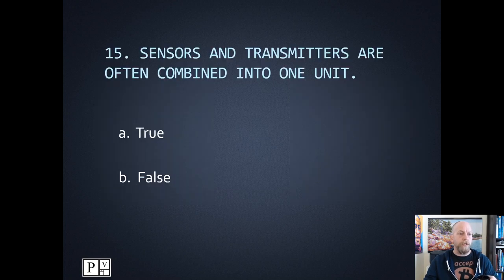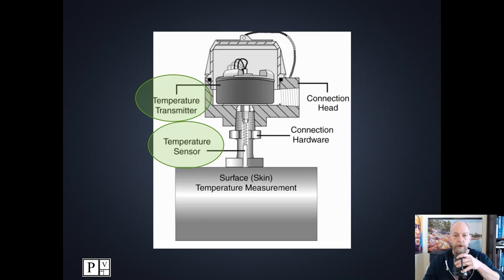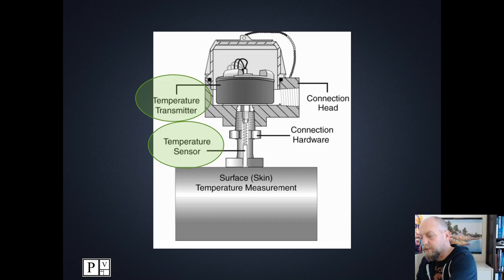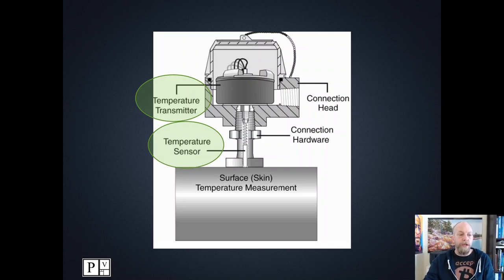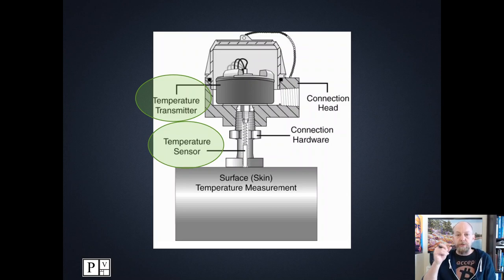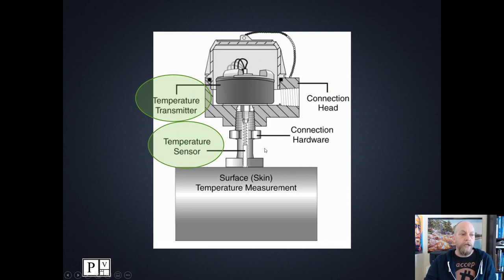Number fifteen: sensors and transmitters are often combined into one unit — that's true. The RTD — a resistance temperature detector — is a piece of platinum wire in a duct or pipe. It changes resistance causing a very small increase or decrease in voltage, which is not a standardized signal. There has to be a standardized signal, and that is the 4 to 20 milliamp output. You're always going to have a transmitter incorporated with a sensor.